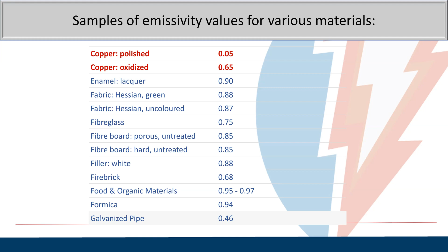This is an example of emissivity values for different materials. You can see how low polished, brand new copper is—about 0.05—which basically won't give you any reflected heat. However, formica, food, organic materials, fiberboard, and other materials are dramatically different. So it's important to understand what you're looking at if you want accurate measurements with a thermal camera.